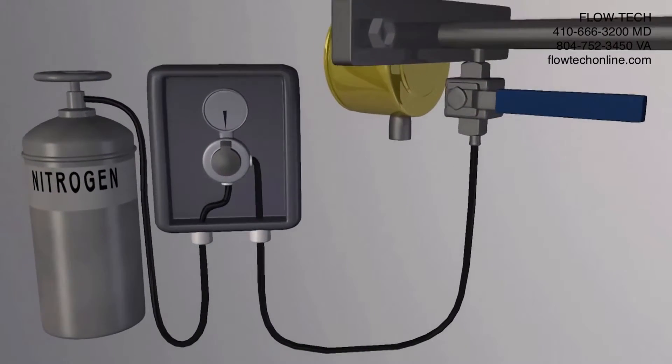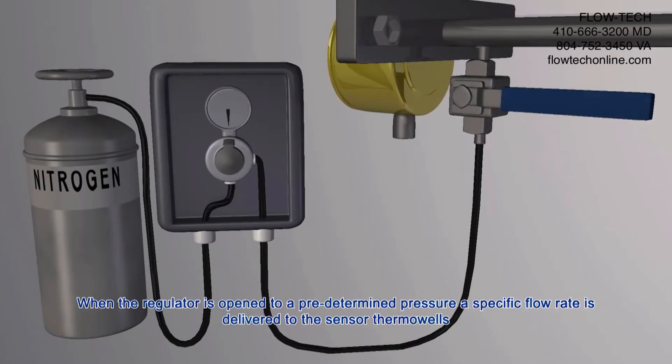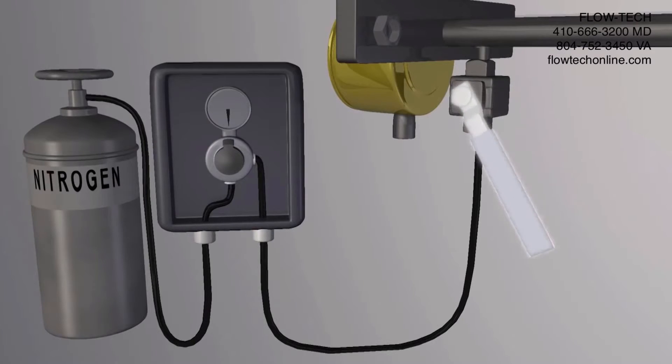The verification equipment required is the test gas — nitrogen — and the connecting hose, which is user supplied, and FCI's Veri-Cal kit. The kit includes a pressure regulator, a digital pressure display, and a hose connecting the meter to the Veri-Cal kit. When the regulator is open to a predetermined pressure, a specific flow rate is delivered to the sensor thermowells through a sonic nozzle.